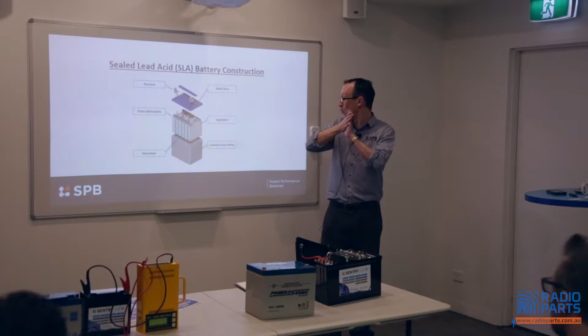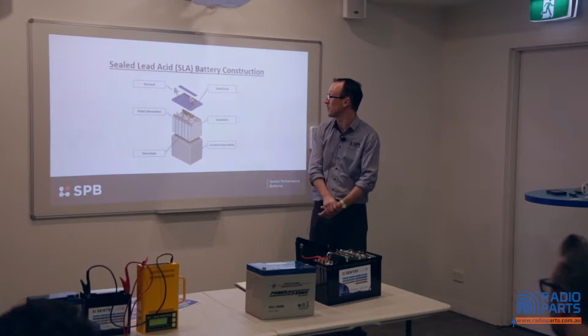When we talk about valve regulated, when these batteries are overcharging or sulfating, or there's chemical activity going on in there, typically they'll gas. But with sealed lead acid batteries, there are safety valves at the top to release it in the event that there is a pressure build-up.